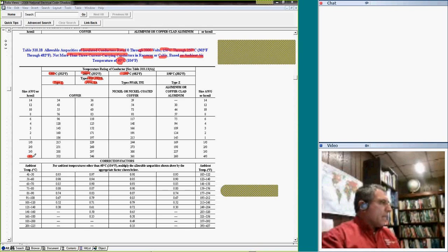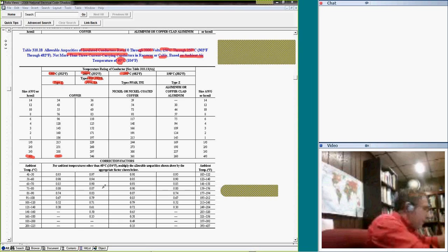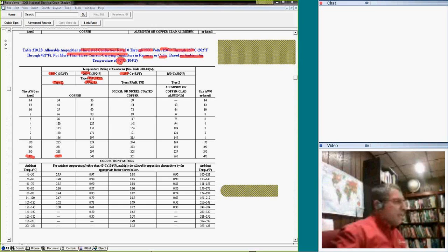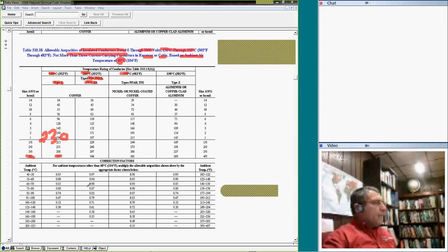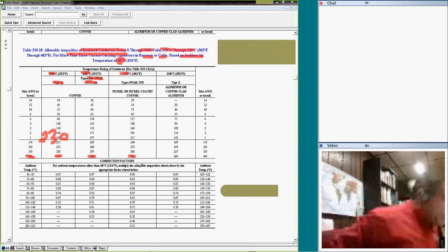Let's look at 4 aught. Insulation is rated for 150. Look at how much 4 aught can carry: 332 amps. To give you an idea, guys, normally 4 aught can carry only 230 amps. And if it's insulation rated 200, you can go higher, and if you use insulation rated 250, you can go all the way to 361 amps.